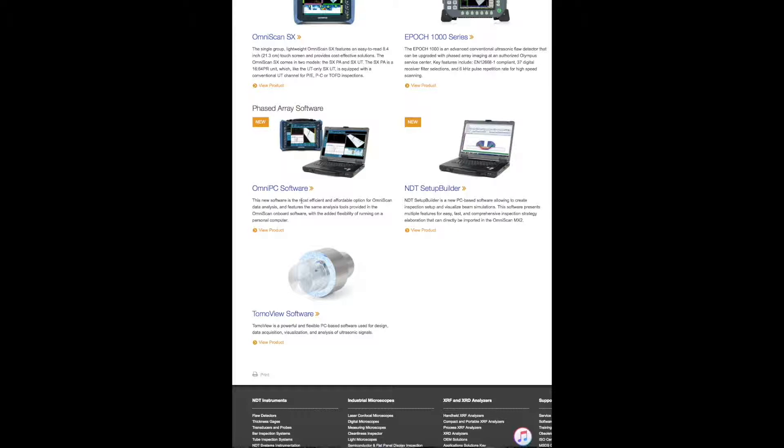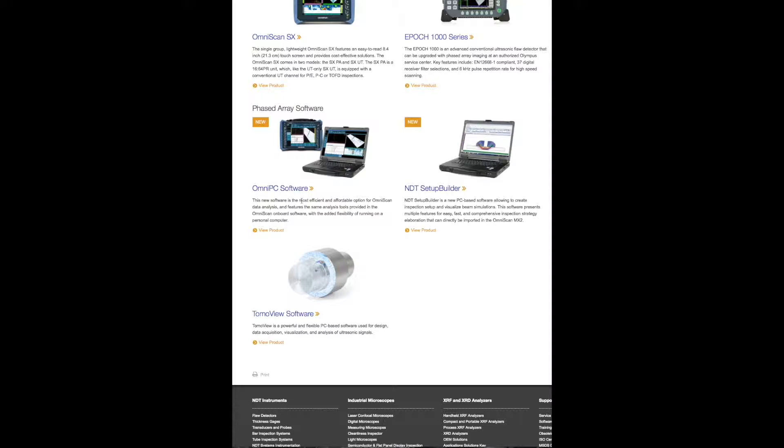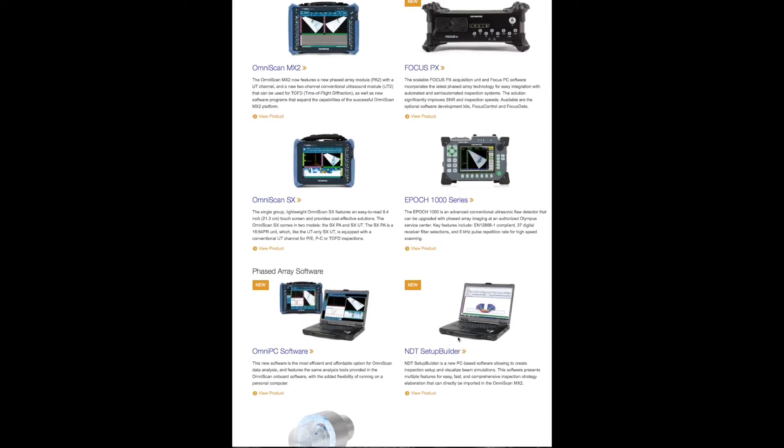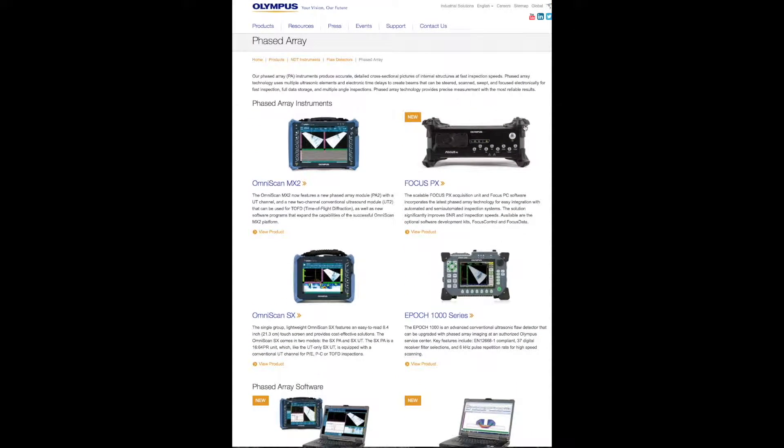The third software that Olympus has is TomoView. TomoView is a comprehensive software which can be used to build setups from scratch, to create focal laws, to import the collected data, to analyze it and make reports. It's a powerful, all-comprehensive software. This is the software you would use if you're using Focus. This is kind of the product line or the family of Olympus instruments for phased array.